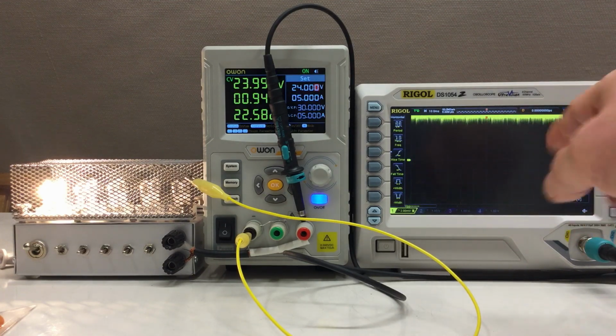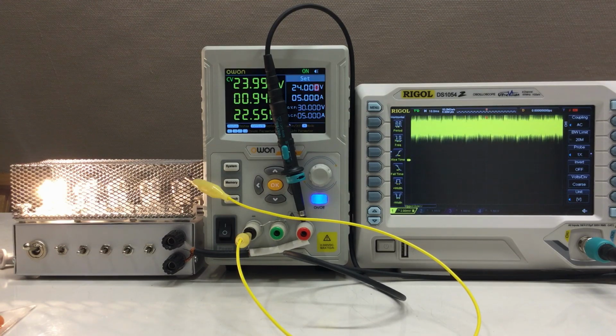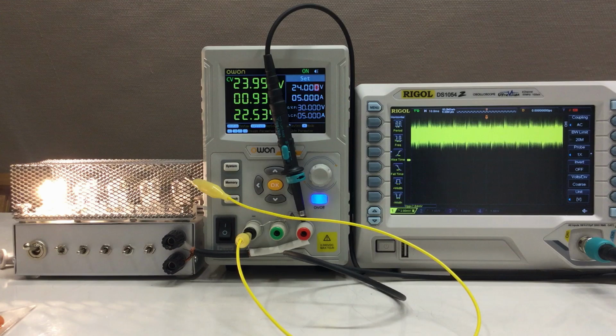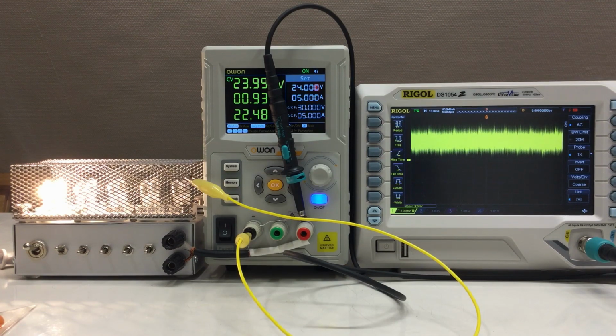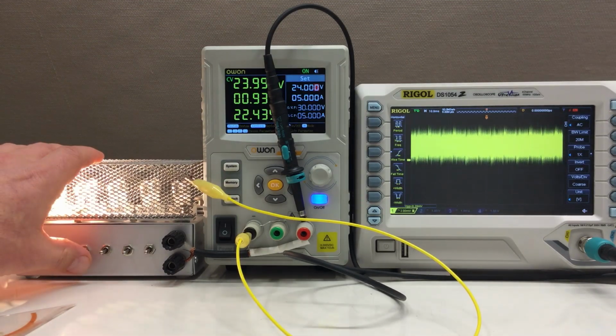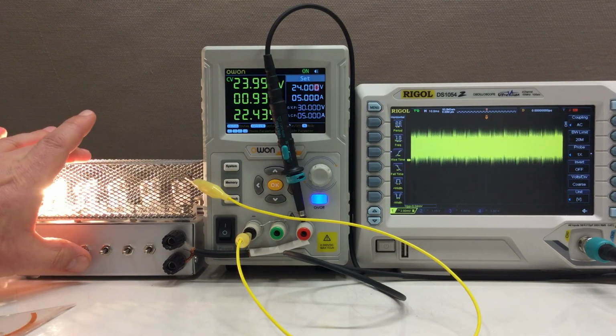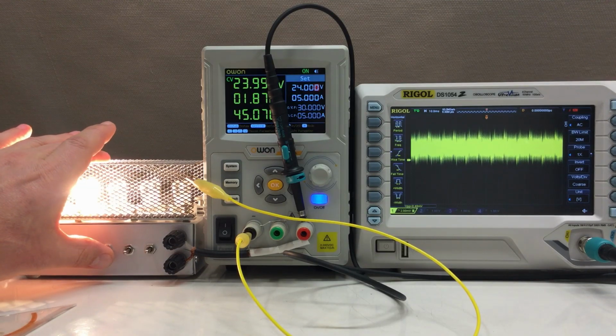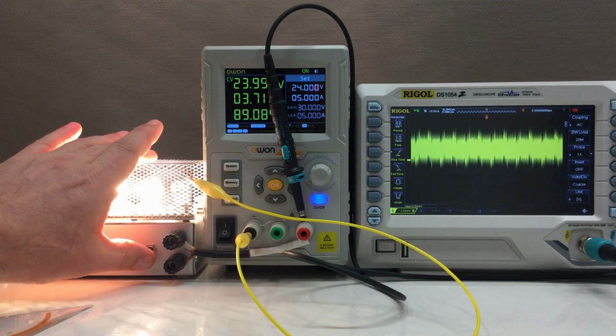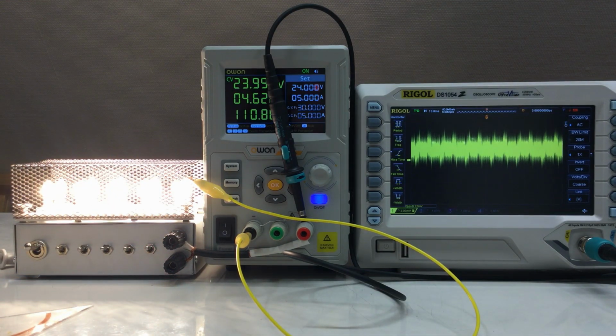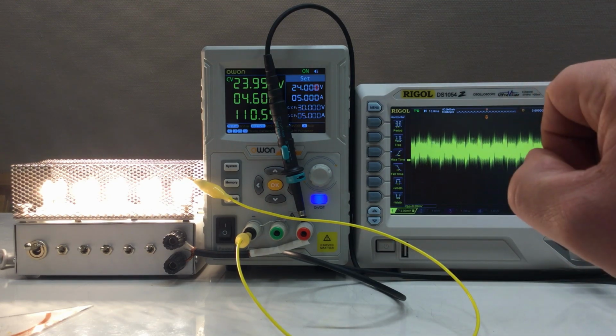It needs a while to recover because we have AC coupling. And I removed my hand. And the noise is a little bit different, but peak to peak, 6, 7, and now we have 7, 8, okay, with about an amp of load at 24 volts. And you see if I put my hand there, it goes up. So let's go for full load here. And now we have between 8 and 9 millivolts. Let's say between 9 and 10 millivolts peak to peak.